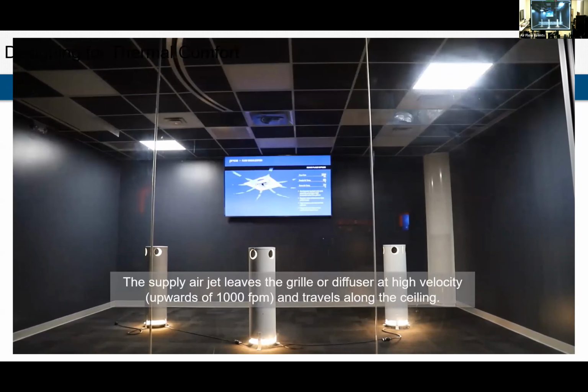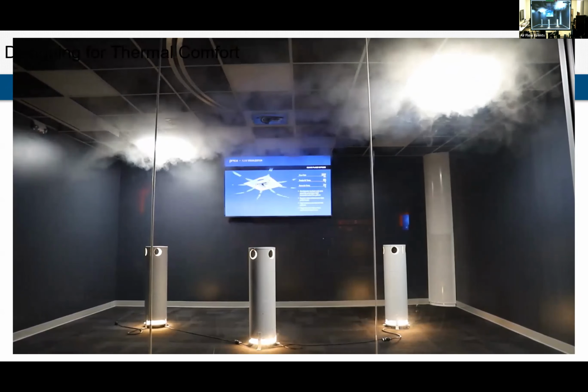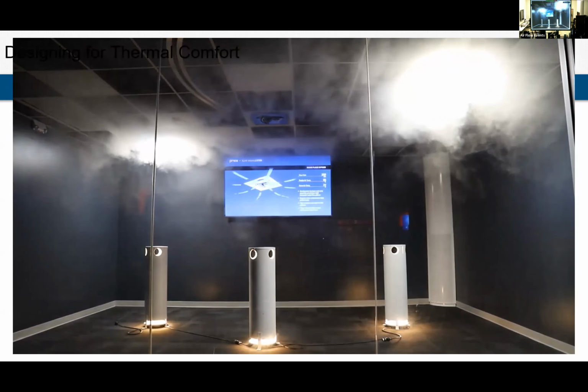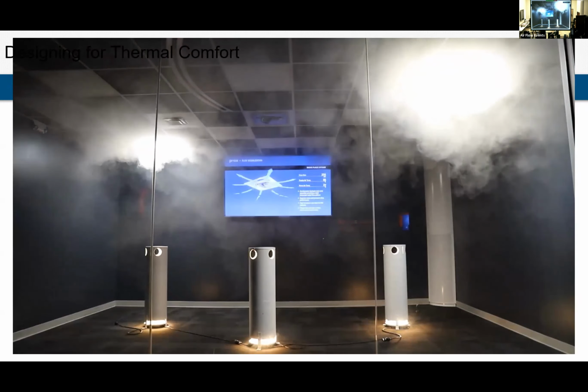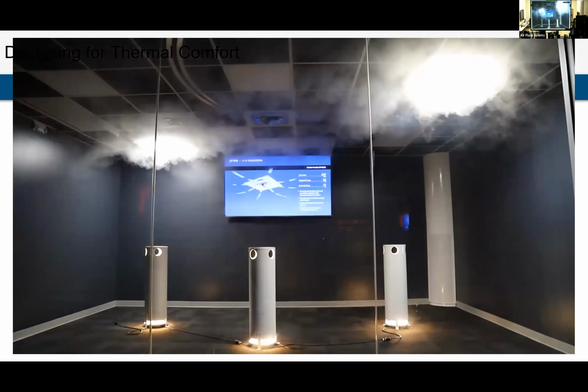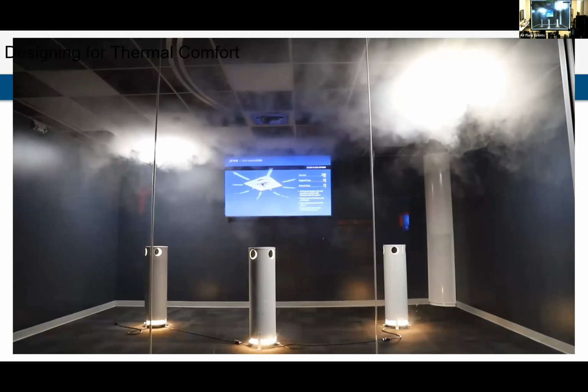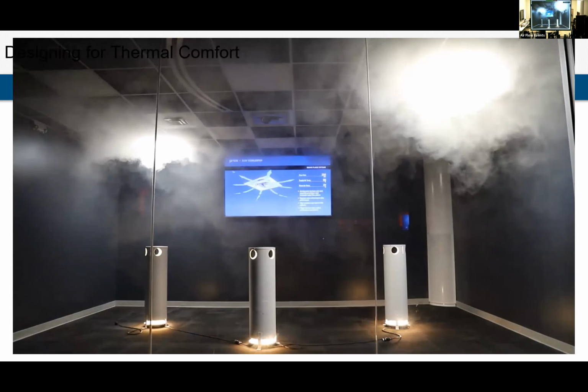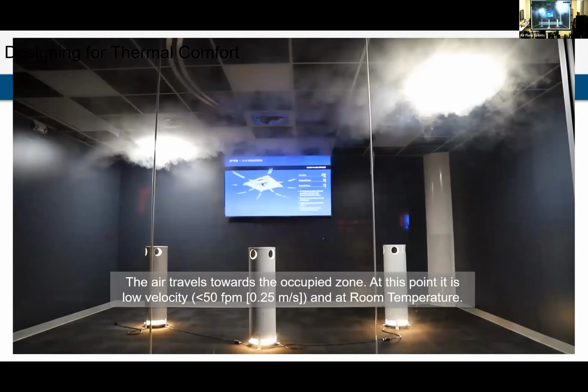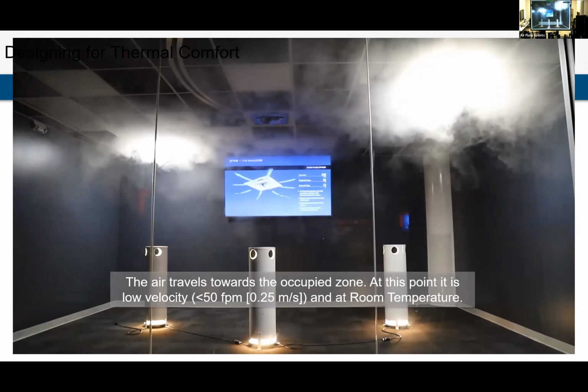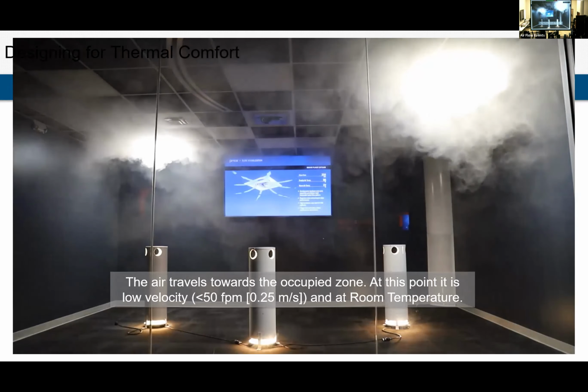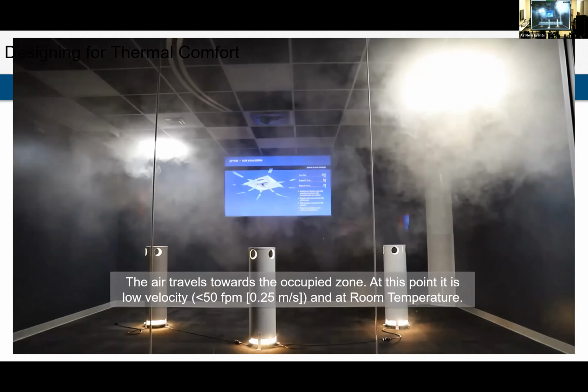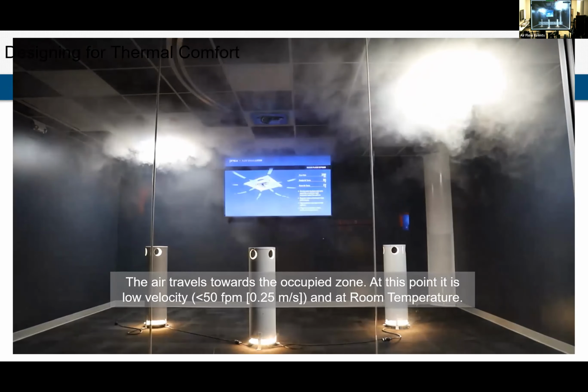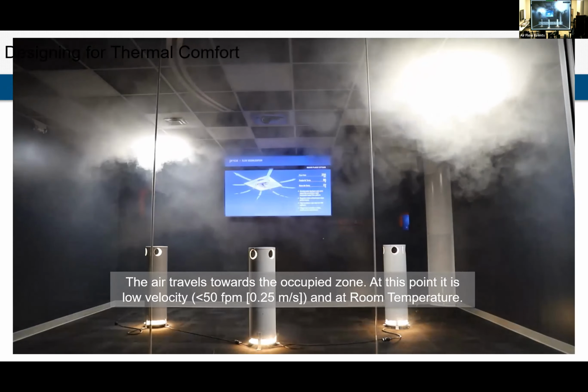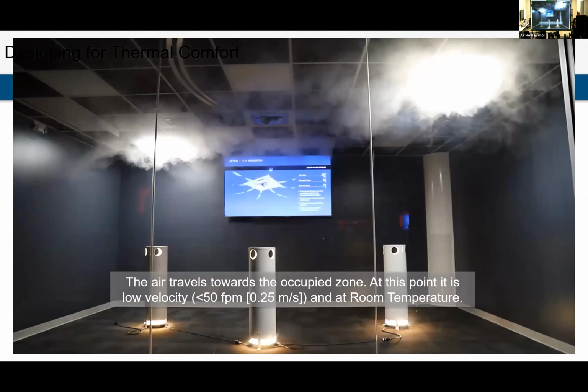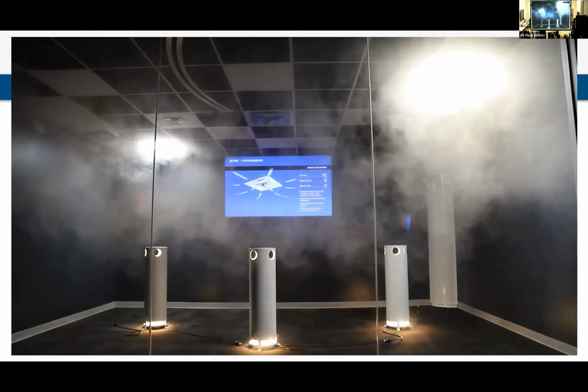Anywhere up to 1,000 feet per minute, it's going to travel along the ceiling. The next step, as that air slows down, it's going to start dropping into the space. It's either going to travel down the walls, or it'll lose contact with the ceiling and just start dropping into the space. This is when it starts to enter the occupied zone. So again, 6 feet off the ground. At this point, ideally, our airflow is at a lower velocity, not super high coming out of the diffuser. We want it down to about 50 feet per minute by the time we start meeting the occupied zone.